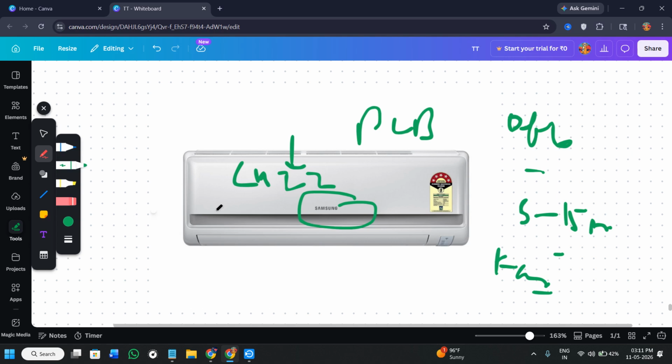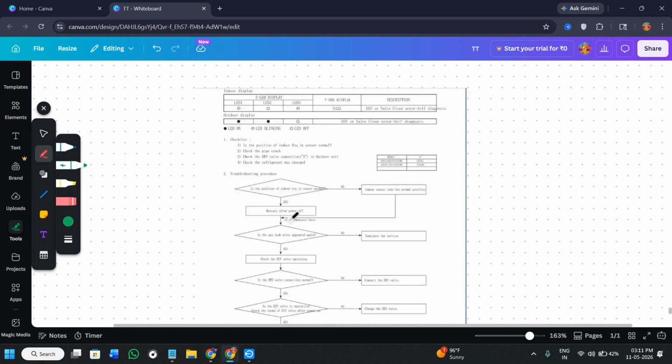may be interrupted. So sometimes loose communication wires between the indoor and the outdoor units can also trigger the C422 error repeatedly. So you need to simply check the moisture exposure, the loose terminal screws and the damaged cable insulation. So this issue is especially common after servicing or electrical storms.